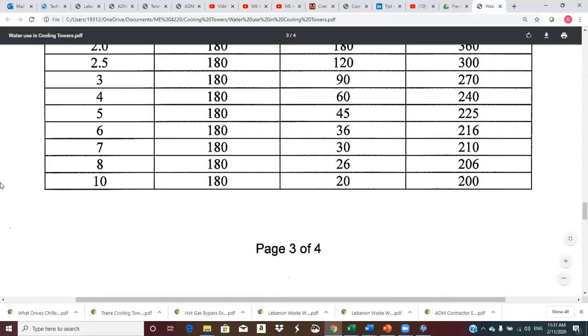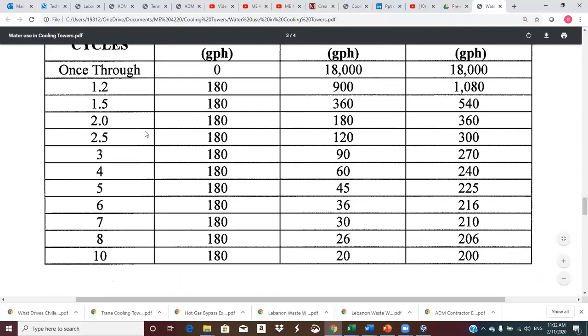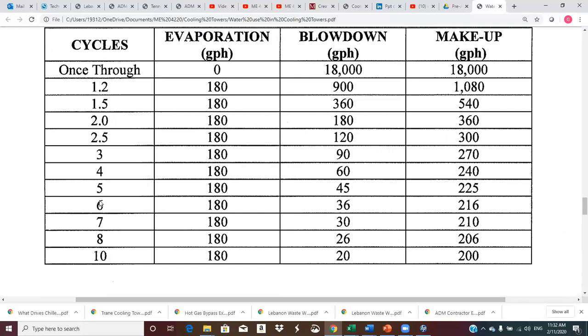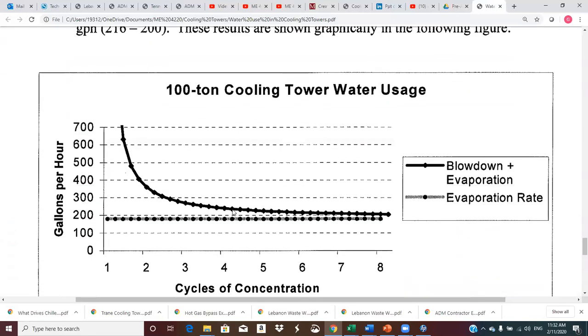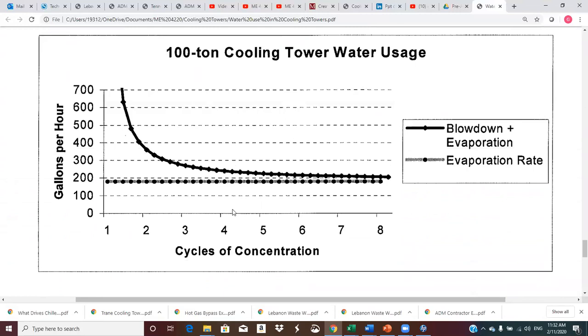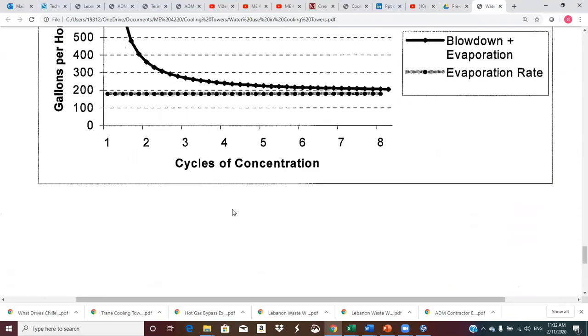If you're already operating, say you're operating at 6 and you go to 7, well, that only saves what, 6 GPM. If you're operating at 2 and you go to 3, that saves 90 GPM. So it depends where you are as far as how many cycles you're running, if you improve by 1 or 2 cycles, how much water you're going to save. Okay. And so this is just a plot of that information. So it shows the blowdown plus evaporation and then just the evaporation.